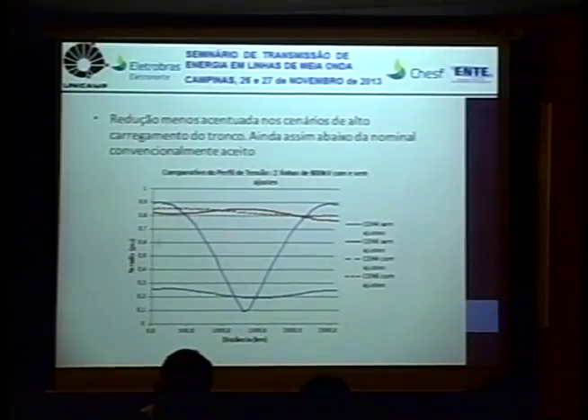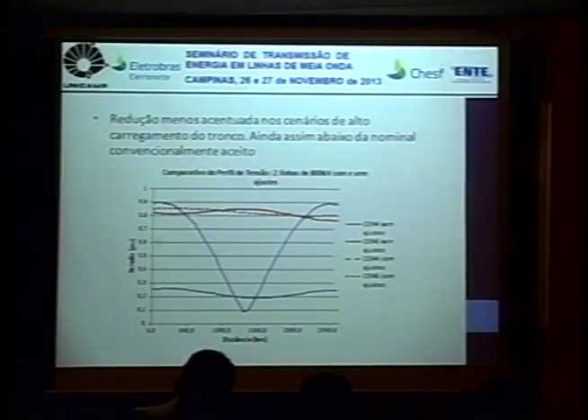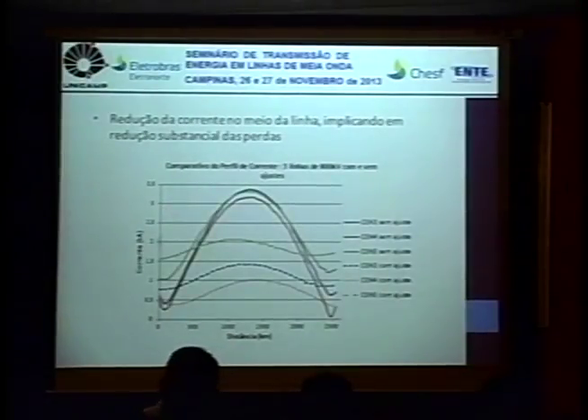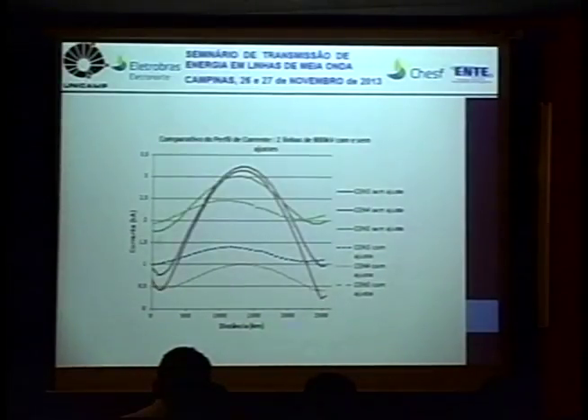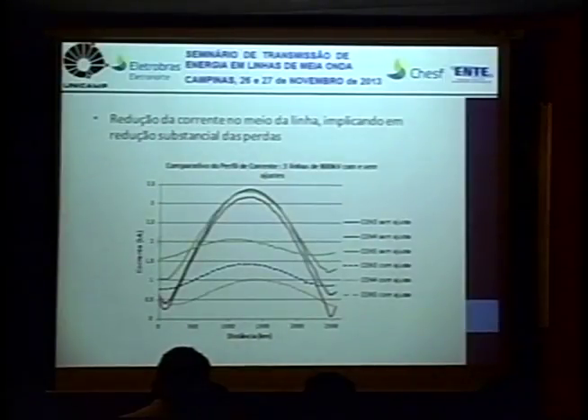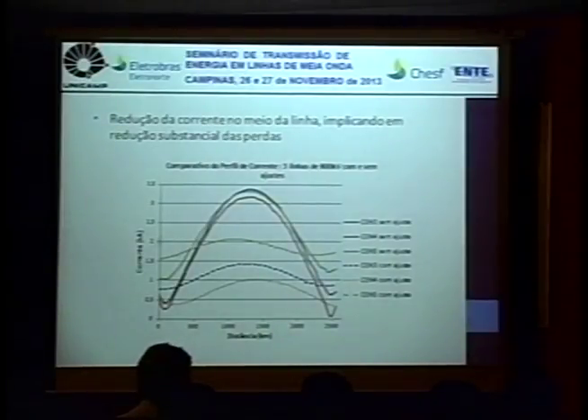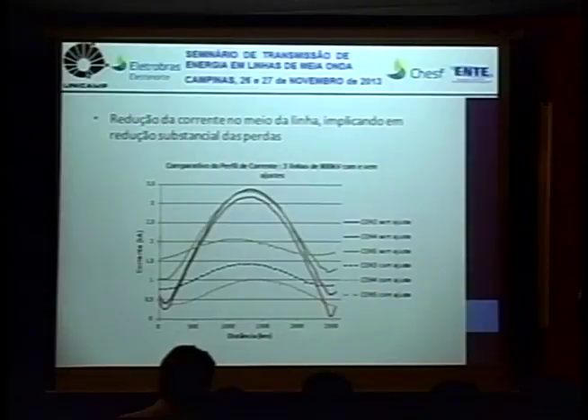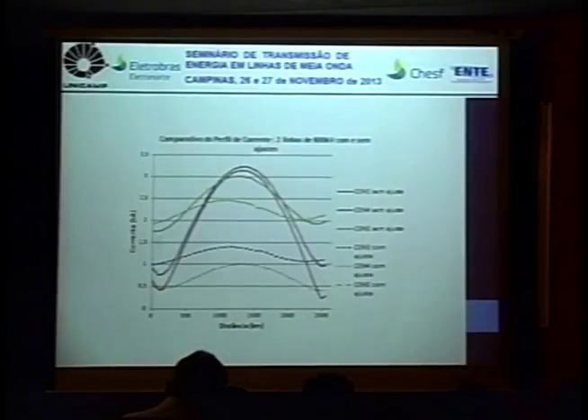The voltage profile loses this wide variation because the line is now close to the characteristic power. The current profile also improves. That's why we have an improvement in terms of losses. The current profile in the middle of the line tends to decrease when you make this adjustment. It's going to increase a little bit in terms of the current profile in the beginning and the end of the line, but it's going to be a more flat current profile. This would be the current profile without the tap adjustment and after the adjustment of the tap.